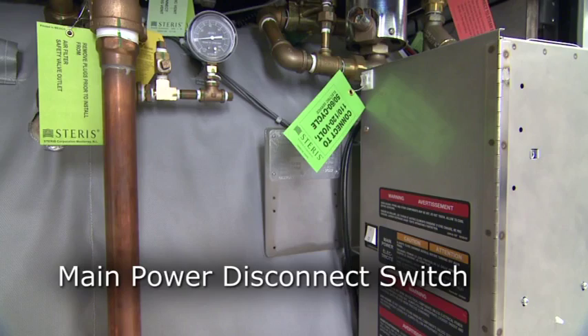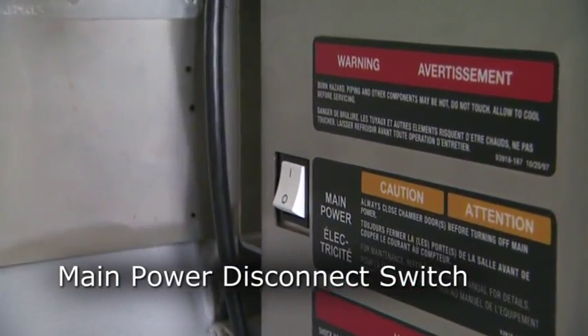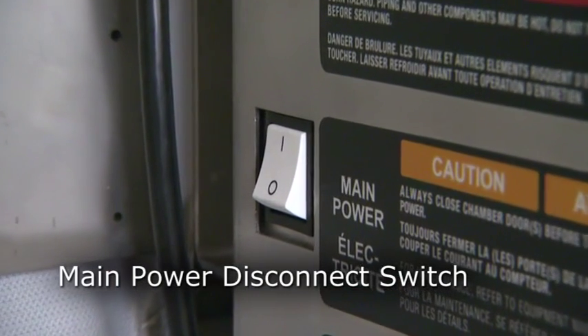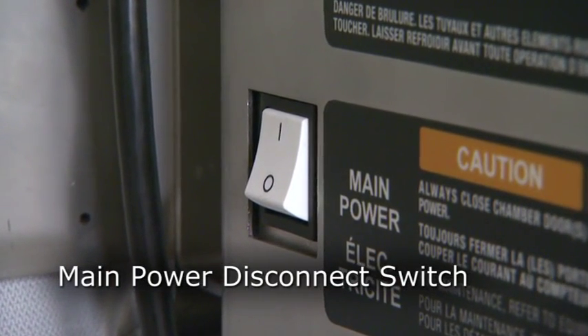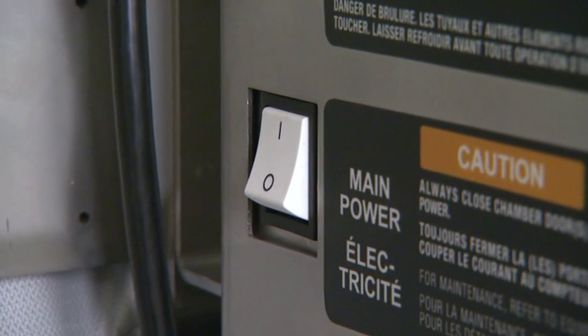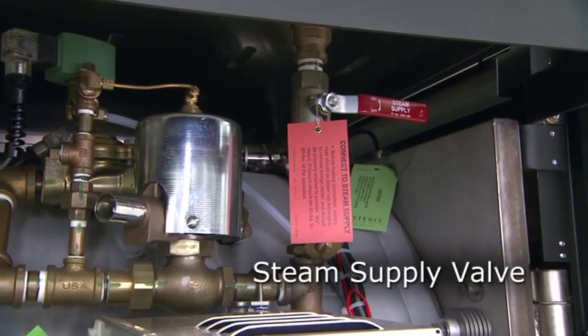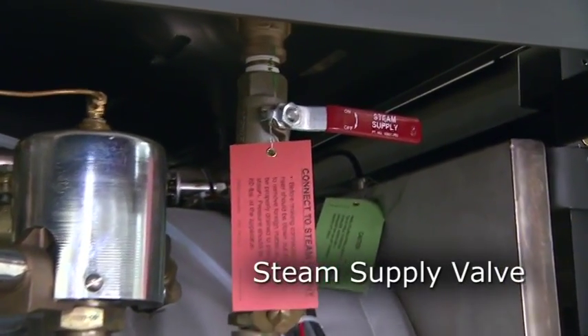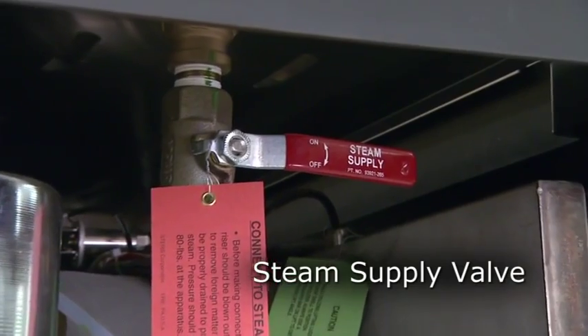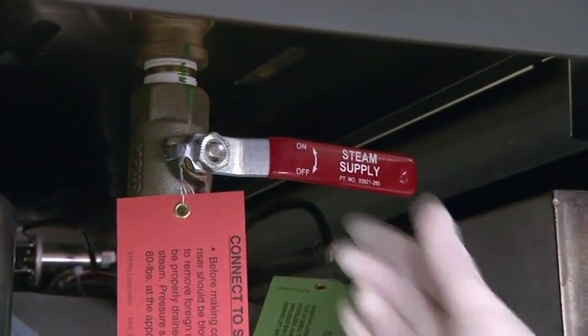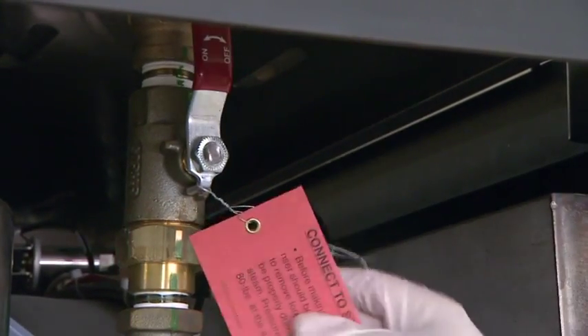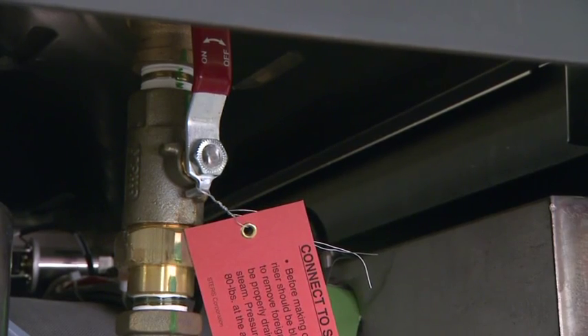The main power disconnect switch is located at the left-hand side of the sterilizer on the main control box. The switch disconnects power to the control. Under normal operation, this switch is left in the on position at all times and accessed only when servicing the sterilizer. The steam supply valve is located behind the side access panel or within the wall enclosure above the chamber. Ensure this is in the open position before trying to operate the sterilizer.